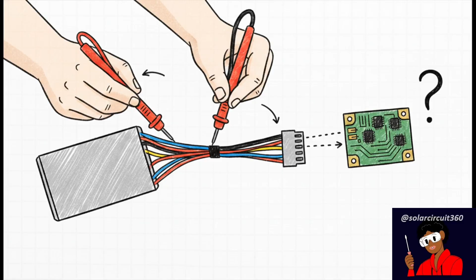Listen closely, because this right here is the exact moment a lot of DIYers completely ruin their project and flush their money down the drain. Before you connect any balance lead to the BMS, you absolutely must verify the voltage order between your connection points with your multimeter. Guessing here is pretty much guaranteed to let the magic smoke out of your BMS, instantly and permanently destroying it.